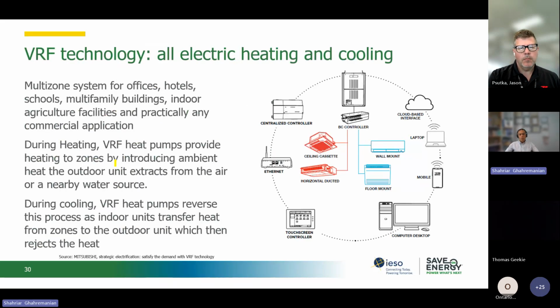So the good thing about the VRF, similar to heat pumps, is that everything is going to be all-electric heating and cooling. And in a VRF system, we don't need a supplemental or auxiliary heating system. So that's a good one that we can benefit from. And as I said, any ceiling cassette, any horizontal ducted system, any floor mount or wall mount fan coils, any of them can be connected to the VRF system, and then they can provide heating and cooling for our facilities.